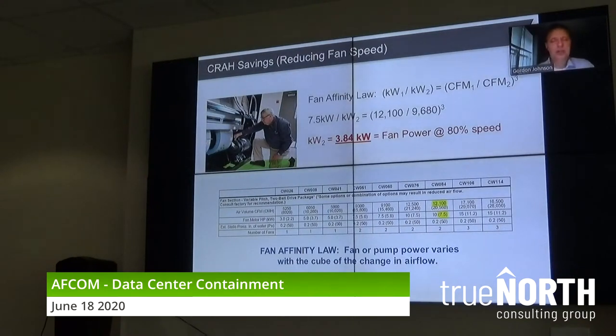Very simply, I mentioned these CRAH units. When running at 100% speed, we're putting out 12,100 CFM, and that shows from the spec sheet that's highlighted. We know their fan power at 100% fan speed is 7.5 kW. However, if you take that maximum CFM divided by the CFM at 80%, which would be 9,680, cube that number, and solve for kW2. I'm going to show you, we're going to make this much easier in just one minute.